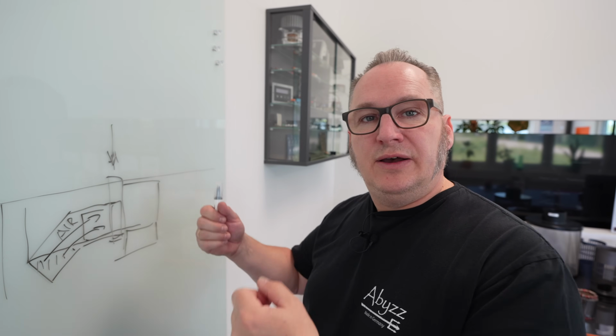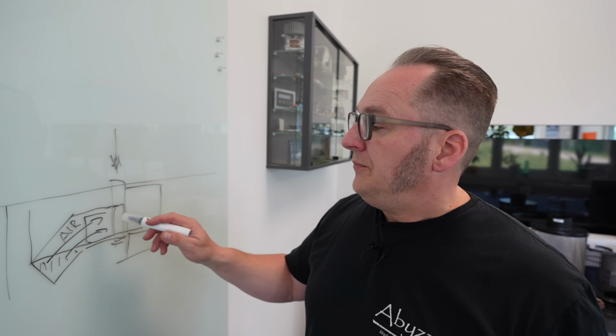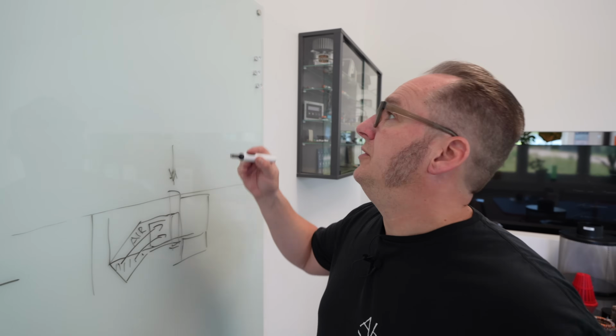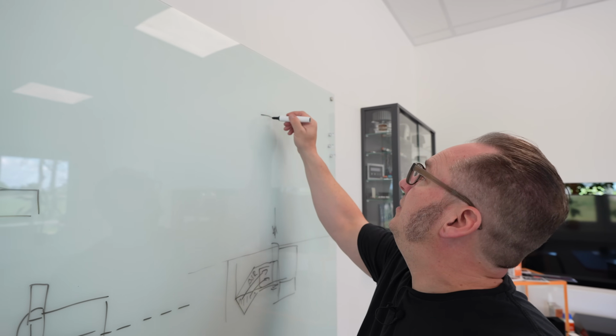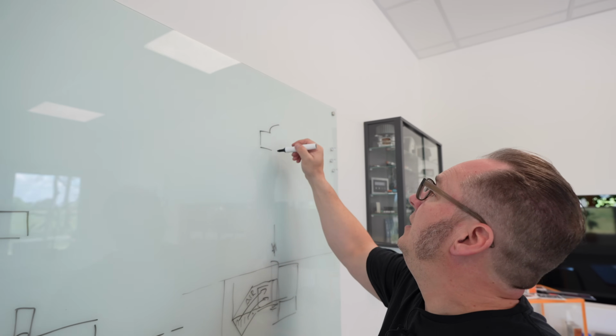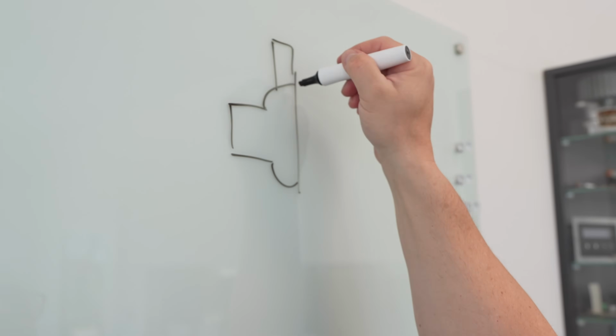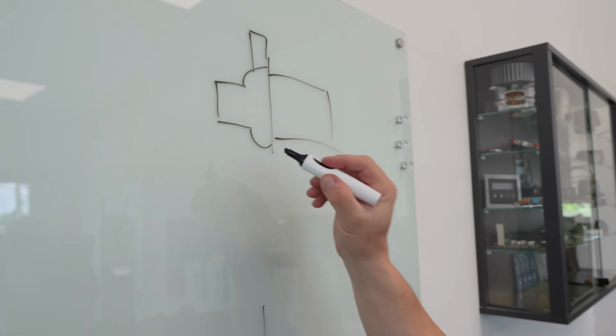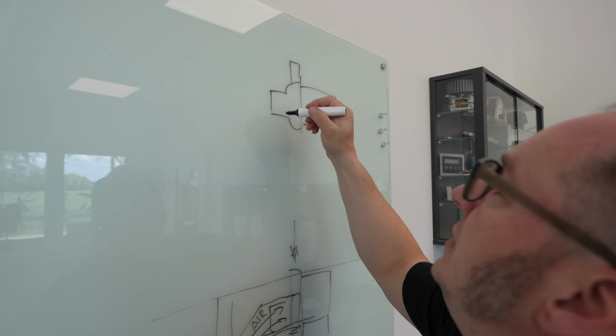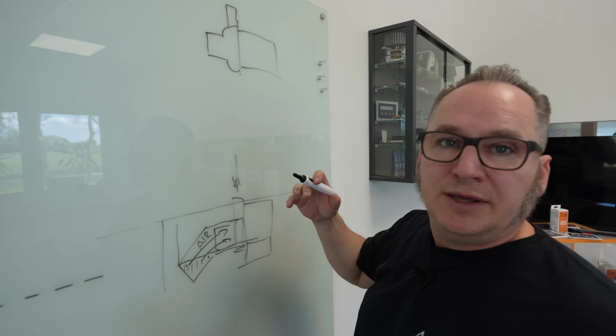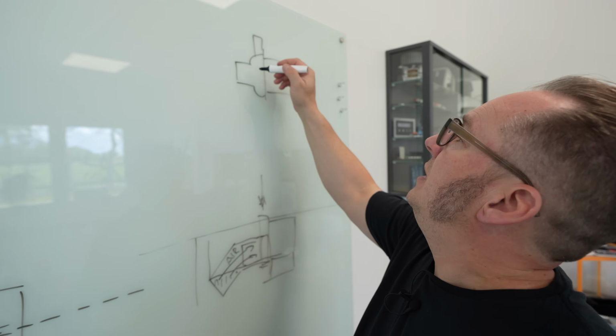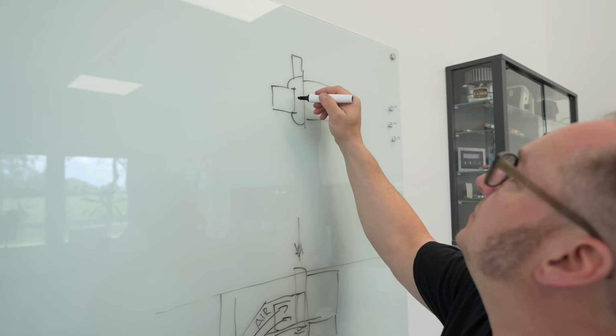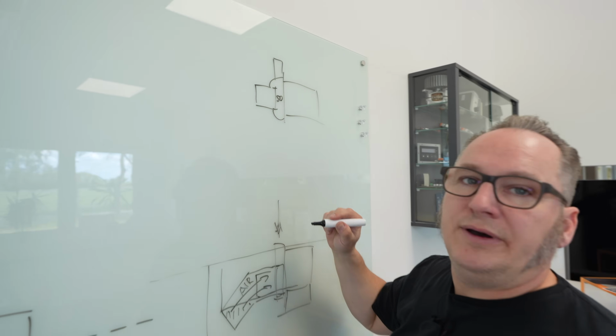If you deliver 14 cubic meters per hour, that's a different story, because then you have a lot more momentum and force on that. To get rid of this, if your sump is big enough, make sure that on any intake, on any pump, and that's valid for pretty much every other pump model as well. So any given pump, let's say you sized your plumbing to be 63 millimeters, and let's say this pump offers 50 millimeter, just like our A200.